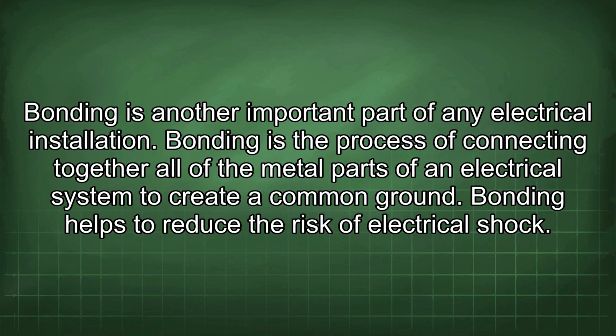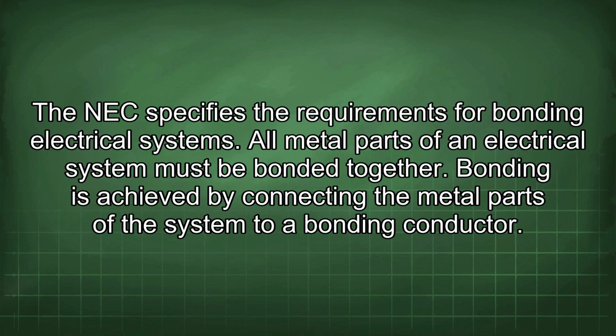Bonding is another important part of any electrical installation. Bonding is the process of connecting together all of the metal parts of an electrical system to create a common ground. Bonding helps to reduce the risk of electrical shock. The NEC specifies the requirements for bonding electrical systems. All metal parts of an electrical system must be bonded together. Bonding is achieved by connecting the metal parts of the system to a bonding conductor.